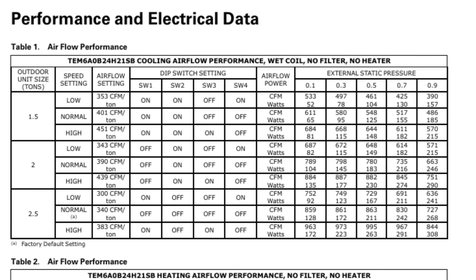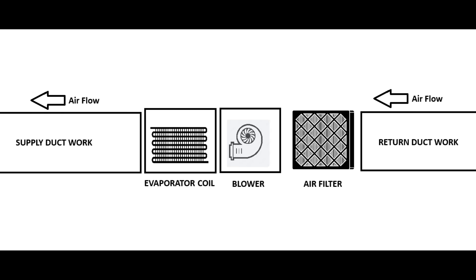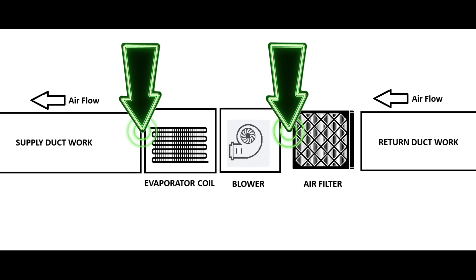If you look at the top of this performance data chart, you're going to see 'wet coil, no filter, no heater.' This tells me they included the evaporator coil in their static pressure test — specifically when it was wet, meaning the air conditioning was running, humidity was condensing out of the air, and the coil was actually wet. That water on the coil is another form of resistance. The chart also says 'no filter,' meaning they did not include the filter in their static pressure test. So in this case, I'm going to place one probe between the air filter and the blower casing, and the other after the evaporator coil before the supply ductwork, and I'll take my reading only when the unit is condensing and making water.